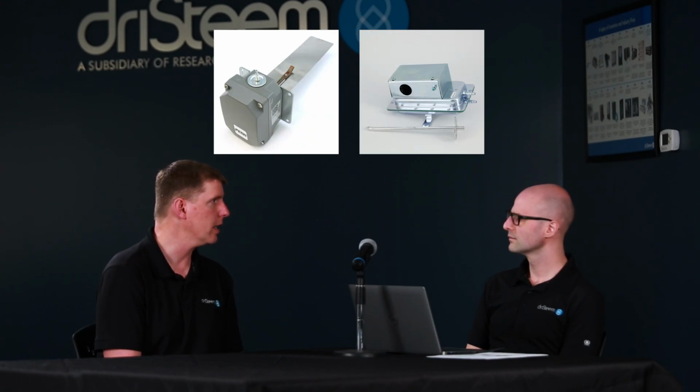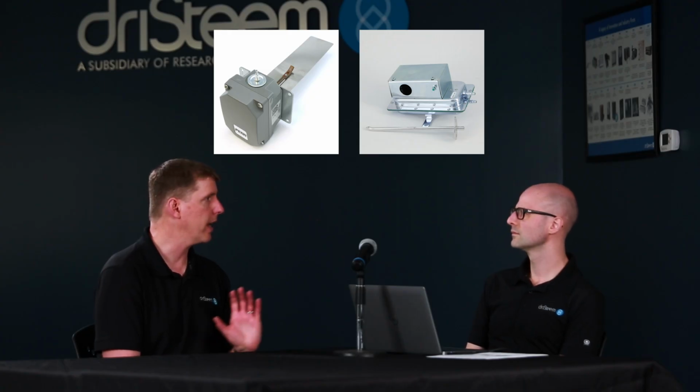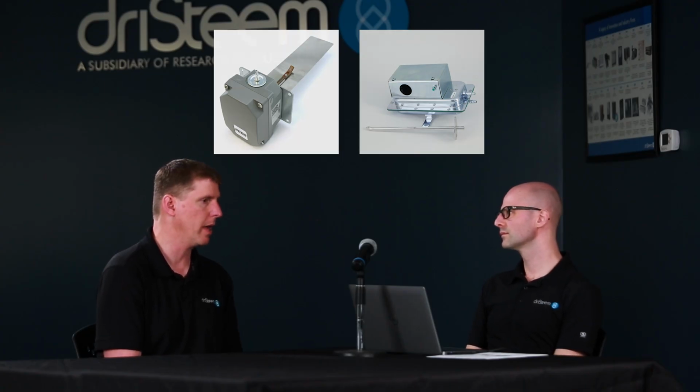All right. Are there any safeties I need to plan for? Key things to keep in mind: if you're adding the moisture and there's no airflow, the steam's just going to stay right where it is. And you don't want it to hit against the walls. The whole goal is to keep it within the airstream. So you want to make sure that you can prove airflow. An airflow switch is commonly done, or if you have another way to know the fans are running, maybe it's a control piece in the air handler you hook into. But you want to make sure that there is air moving through so you can add that moisture to it.